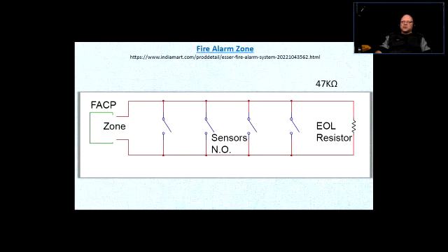Of course there will be some conversation. Is there a fire? No, there's not. So they would dispatch a technician to see what's wrong with the system, and usually it would be a ground disconnected from the stations, or it could be a break in the wire.